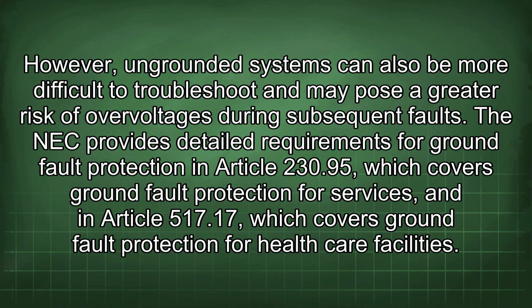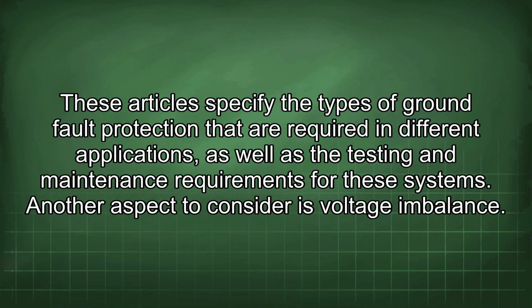The NEC provides detailed requirements for ground fault protection in Article 230.95, which covers ground fault protection for services, and in Article 517.17, which covers ground fault protection for healthcare facilities. These articles specify the types of ground fault protection that are required in different applications, as well as the testing and maintenance requirements for these systems.